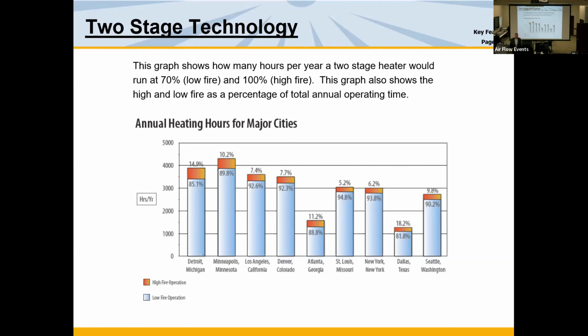Steady state operation. That's right. You don't start and stop. Now you think about a radiant heater. It takes about 5 to 7 minutes before the tube comes up to temperature. And that's wasted energy. You're not emitting any radiant heat, but you're burning gas. The minute the gas valve turns on, you're burning gas. Okay, so the idea with two-stage is to stop the cycles. So if we reduce the cycles, and typically with our two-stage, it's 35% reduction, it ends up meaning less energy is wasted in the heating up and cooling down process of cycles. Make sense? All right, next slide.